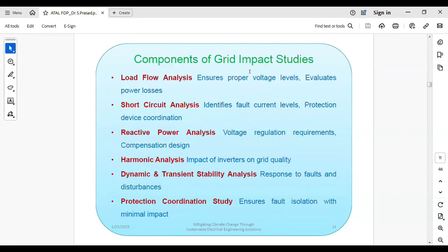So these are the different components of grid impact studies. That means what are the different studies that need to be conducted when an RE developer is going to install a PV plant. First is load flow analysis, which ensures proper voltage levels and evaluates power losses and transformer overloading. Are voltages at all the buses within limits, suppose 0.95 to 1.05 per unit, can you maintain that at all the buses? And what are the losses happening? Transformer overloading and cable overloading can also be ensured from the load flow analysis. Therefore the energy consultant, the power engineer, has to conduct the load flow analysis, and the report has to be submitted.